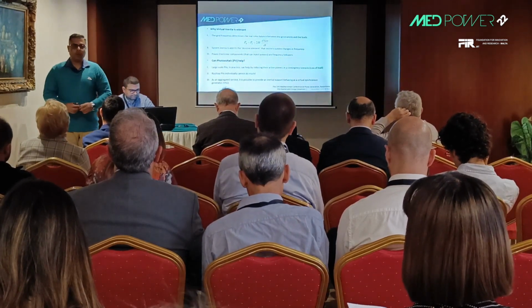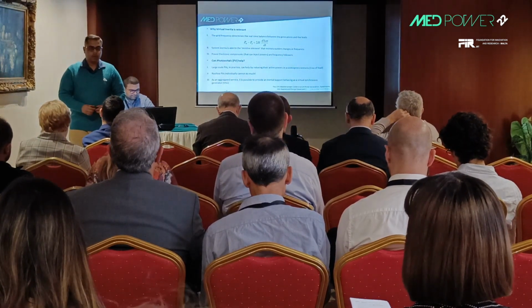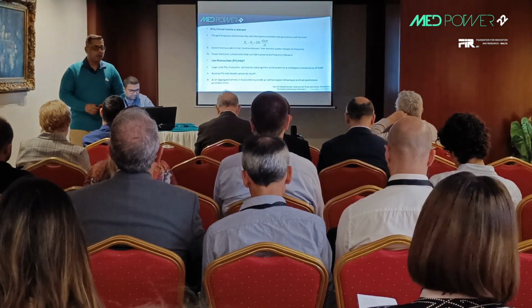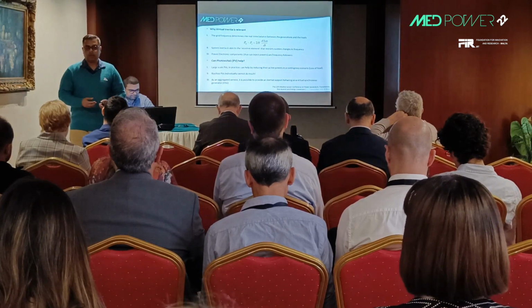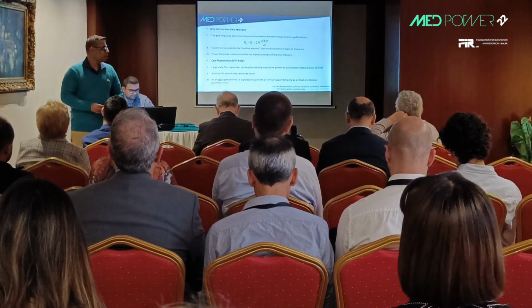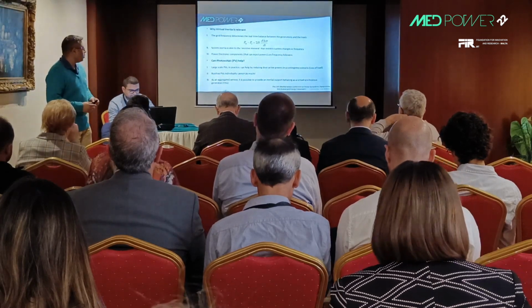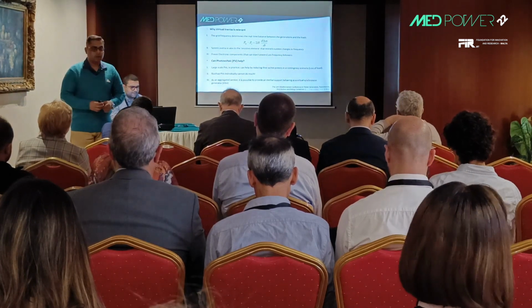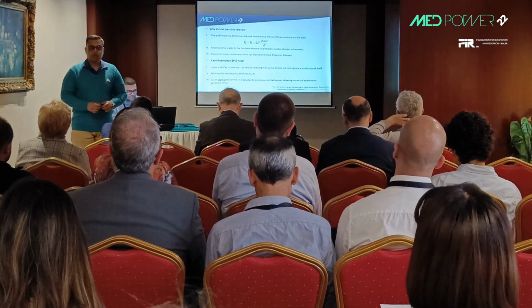So now to come to why virtual inertia is relevant and why it is important. The grid frequency in an AC system essentially determines the real-time balance between the generation and the loads. When we have an event such as a fault, a loss of load, a loss of generation or just a load change, the swing equation comes into play, and the difference determines whether the generator is going to accelerate or decelerate.